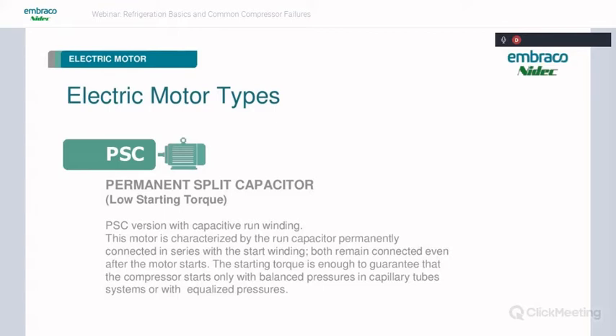A lot of your newer air conditioning systems are using TXV valves. So with this type of motor, you would need to add a start relay and a start capacitor if you had a TXV valve, or some of the TXV valves that they use for air conditioning are externally equalized that help the system equalize in the off cycle to get around that. Or a lot of the compressors nowadays are using scroll compressors, which are sort of high starting torque by design, because the scrolls start unloaded, and then once the compressor started, they load up. So that's kind of how we get around that. But this is more of your air conditioning motor, the PSC motor.